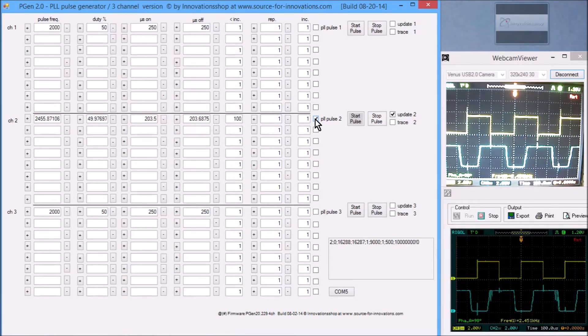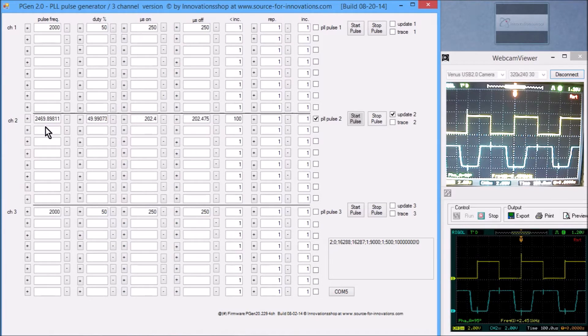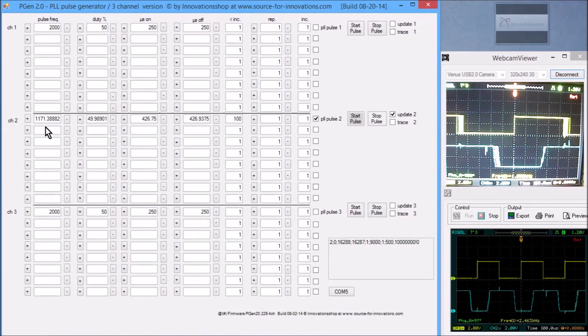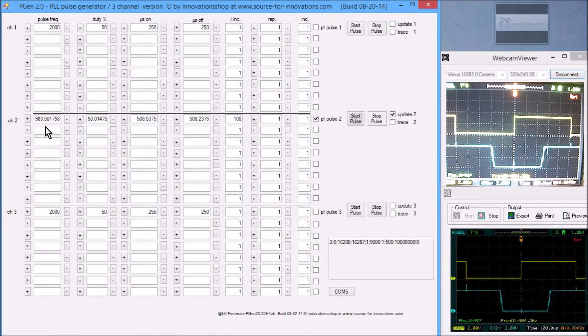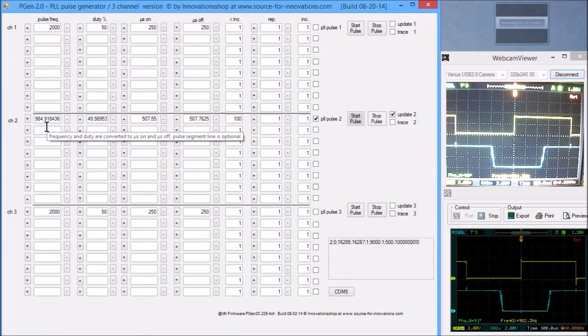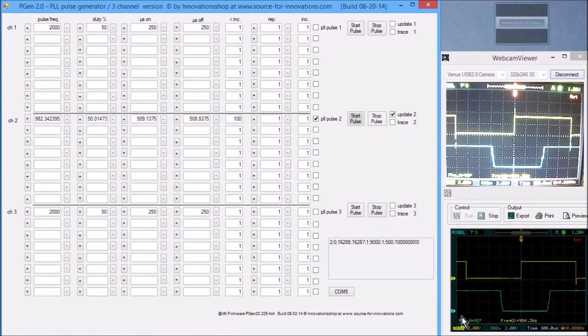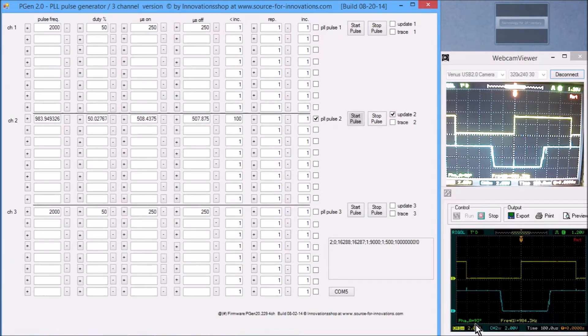Now we see how the system behaves when the PLL function is activated. The frequency is at approximately 2460 Hz. When I push the first button there is a large change in frequency. The frequency reaches approximately 981 Hz — this frequency was adjusted by the pulse generator observing the feedback signal until the phase angle reached 90 degrees.